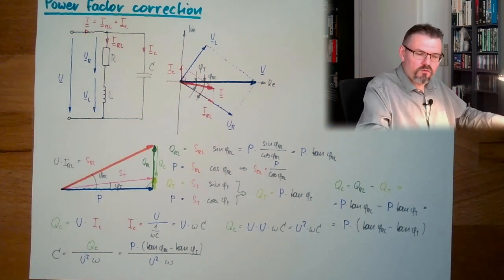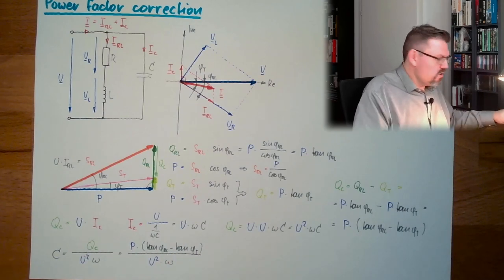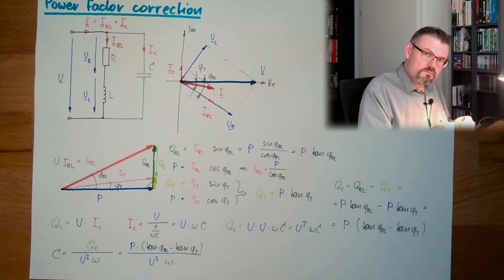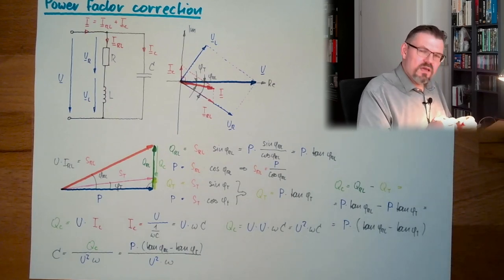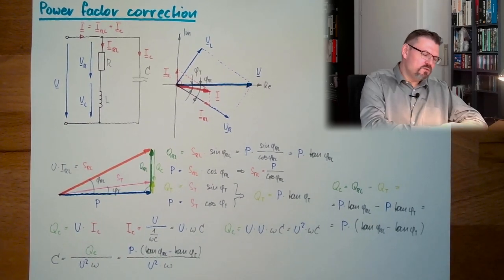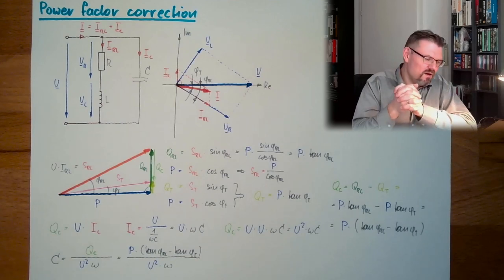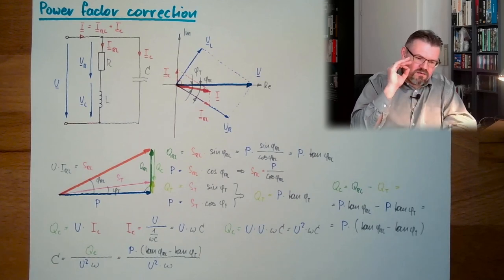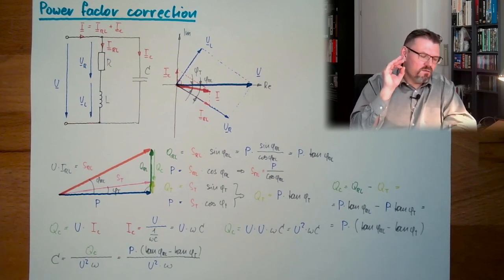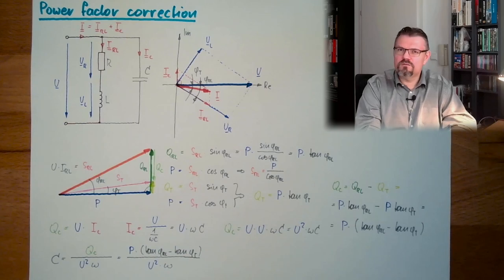Of course, you could say my target phi is zero, then this would also lead to the correct value, whatever you like. It's not always recommended to go to zero. Sometimes you want to stay a little bit in one direction. This depends a little bit on the situation in the network. So this is why I said there must be a target phi, a total phi, a target phi must be there, so that we can easily calculate our needed capacitor for correcting our power factor to a more pleasant situation for our network. And now our network operator is satisfied.